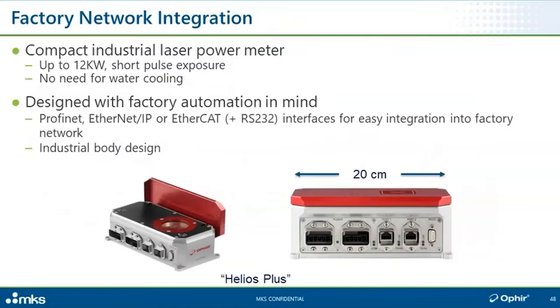Okay, regarding the challenges of making a monitoring solution suitable for industrial environments, besides footprint, we also mentioned factory integration. So now let's just briefly look at some self-contained instruments. These make use of the pulse power concept, but they do it automatically. They measure the exposure time using a built-in photodiode. So here's a device, we call it the Helios Plus. It's actually a family of devices. It's 20 centimeters long, it's small, so obviously it's not massive and it's not water-cooled. And you'll notice the industrial body, there's a protective cover that is remotely opened when it's time to take a measurement so that the rest of the time the sensor's window is protected from process debris.